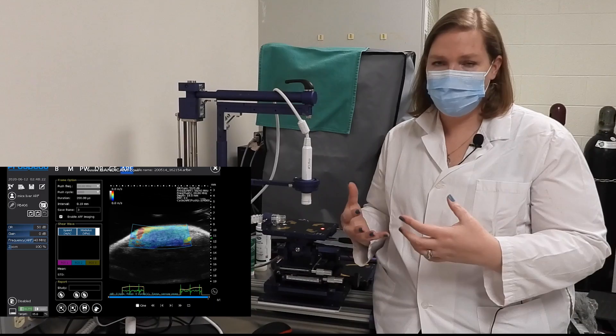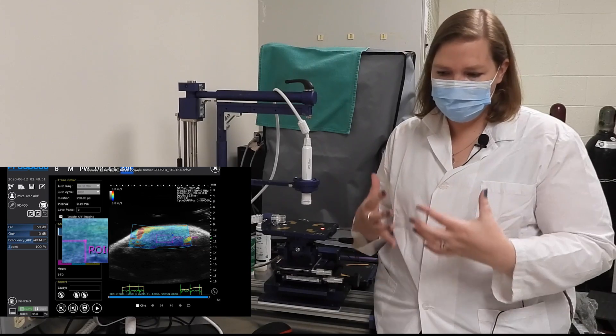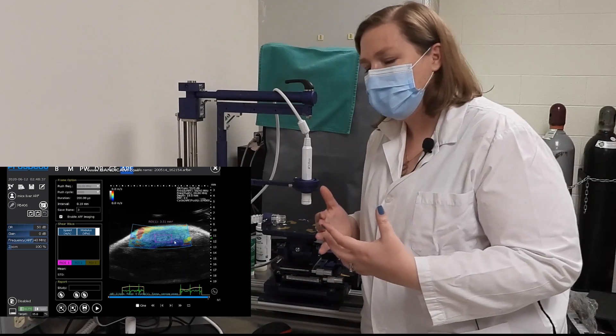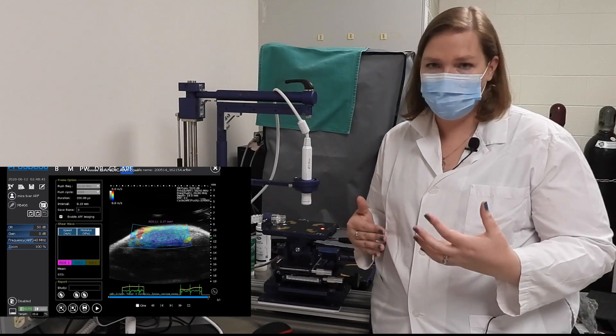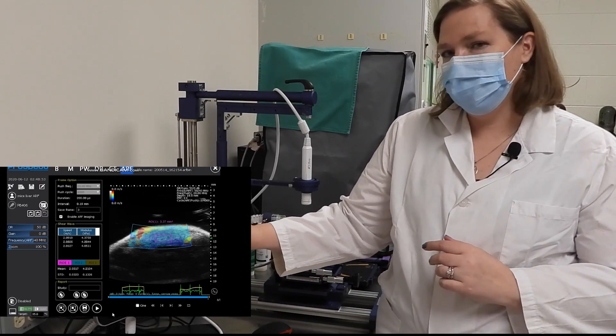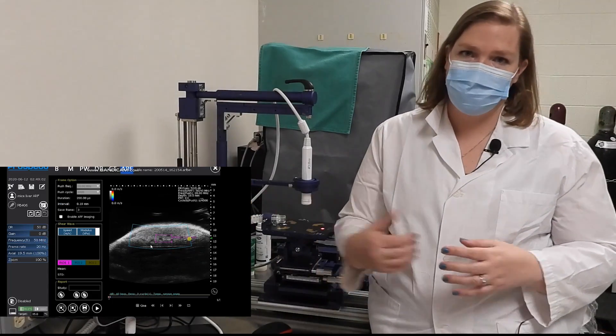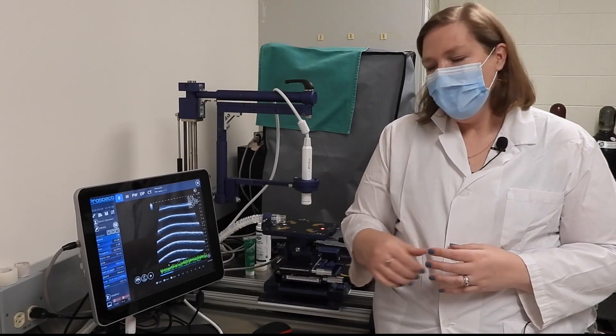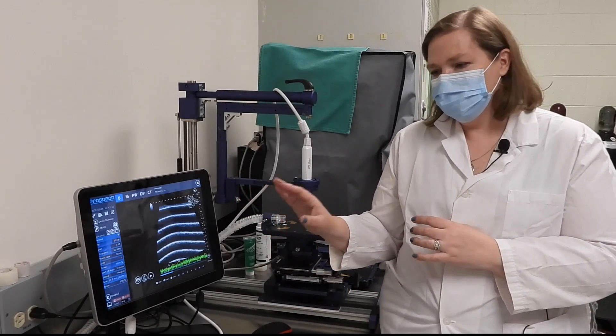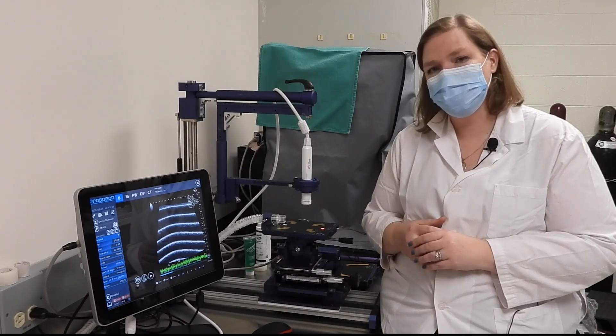For global changes such as hepatic fibrosis or fatty liver affecting the parenchyma, the speed of sound through that liver will be quite different from normal. Within the software, you place a grid over the structure, and after analysis a color overlay is applied showing the speed of sound through that tissue and highlighting areas of change. You can draw multiple regions of interest and program the system to average over multiple pulses.